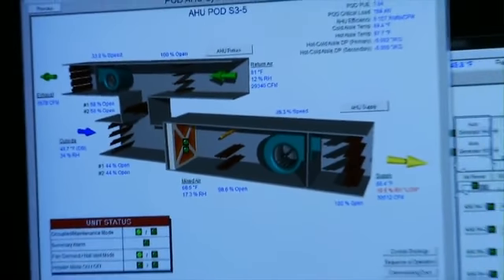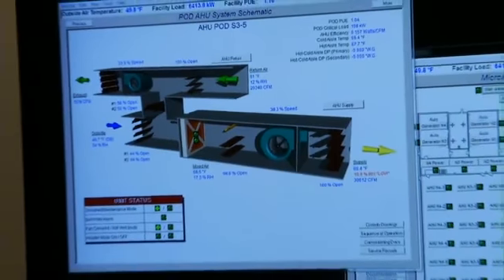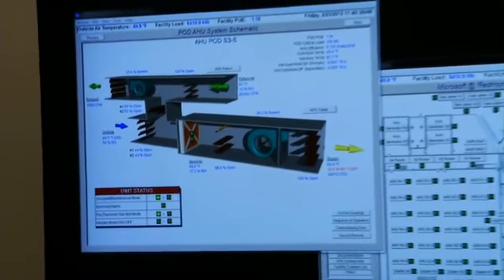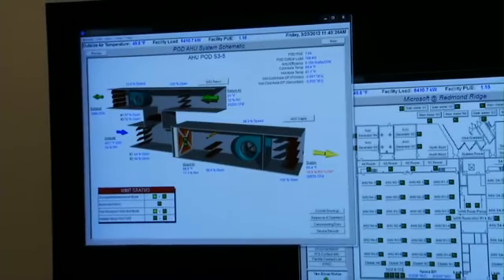When it's too cold outside, we can reuse the warm air from the exhaust of the IT equipment to mix with the cold air and produce a consistent temperature throughout the winter months. There are no traditional chillers or air conditioning systems in the environment.